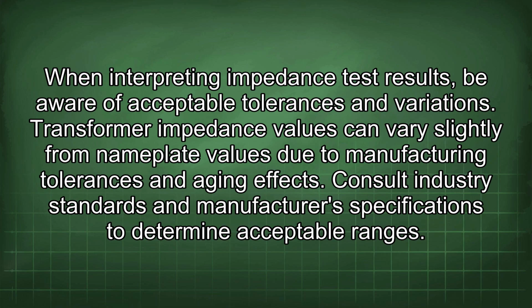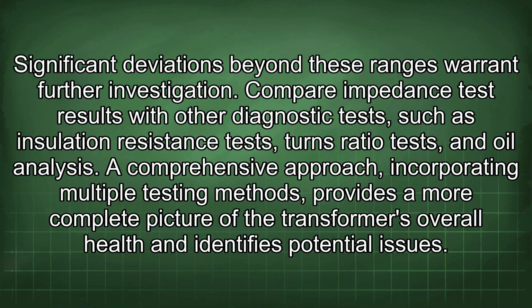When interpreting impedance test results, be aware of acceptable tolerances and variations. Transformer impedance values can vary slightly from nameplate values due to manufacturing tolerances and aging effects. Consult industry standards and manufacturers' specifications to determine acceptable ranges. Significant deviations beyond these ranges warrant further investigation. Compare impedance test results with other diagnostic tests such as insulation resistance tests, turns ratio tests, and oil analysis.